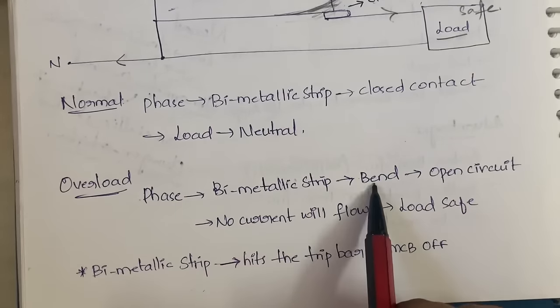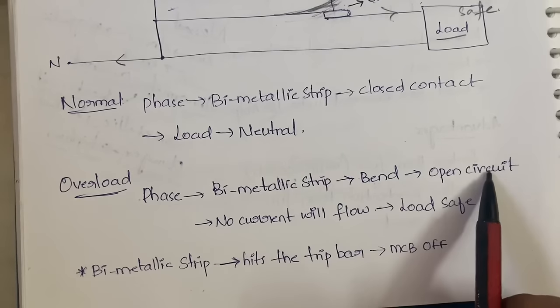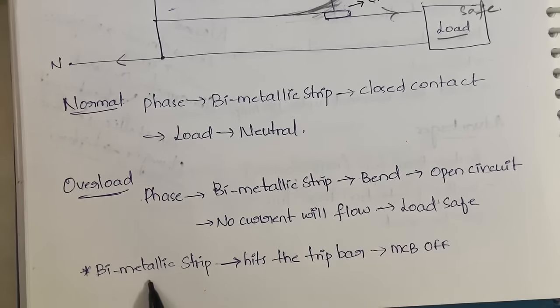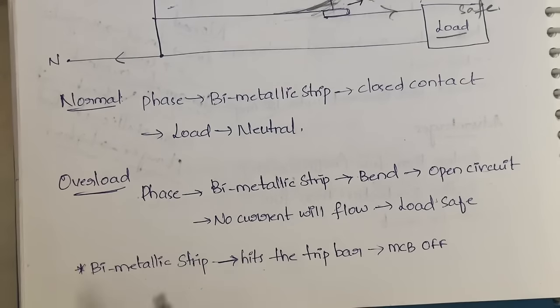To summarize overload protection: current flows from phase to the bimetallic strip; the excess current heats the strip, it bends and the circuit becomes open so no current flows and the load is safe. The bimetallic strip also hits the trip bar, which displaces and turns off the MCB switch.